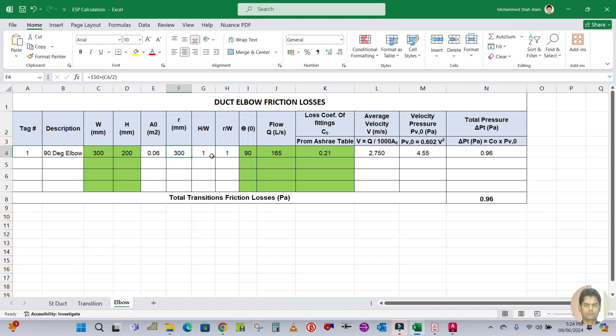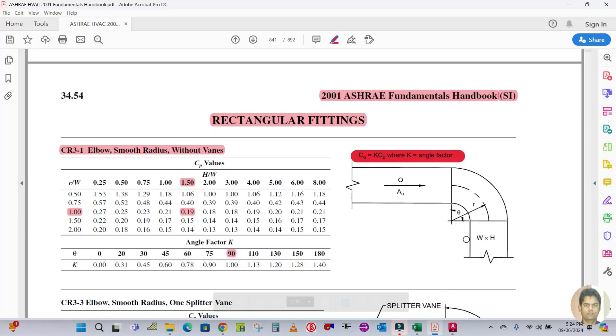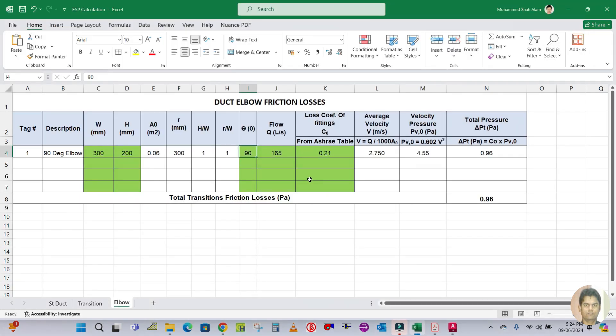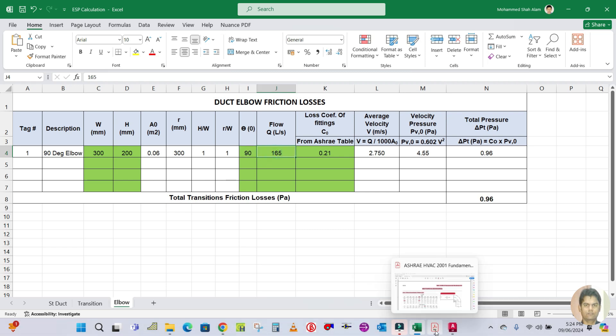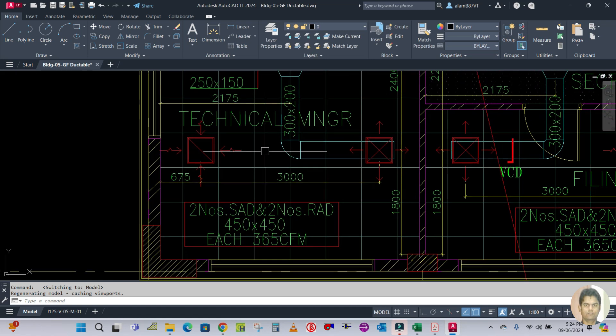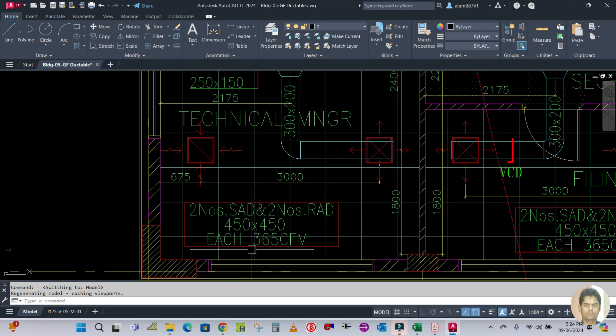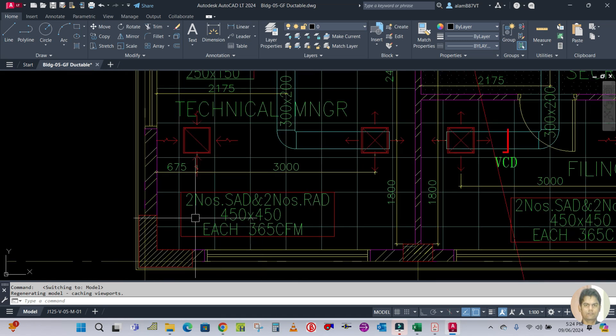H/W is height divided by width, and R/W is calculated the same way. The degree is 90 degrees or 45 degrees — enter whichever applies for this elbow. For flow, I calculate from the drawing: there are two supply air diffusers (SAD) and two return air diffusers (RAD), each 450×450, each at 365 CFM.